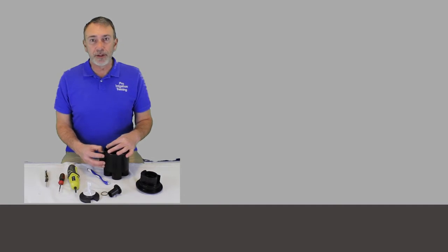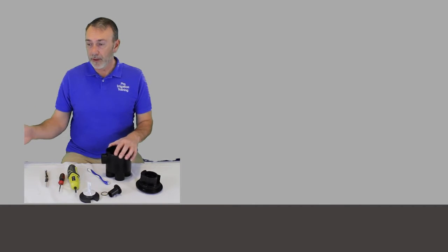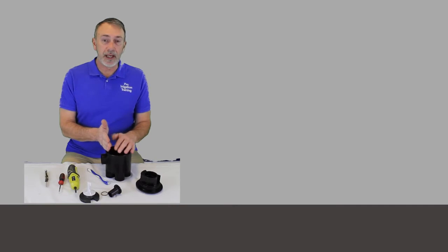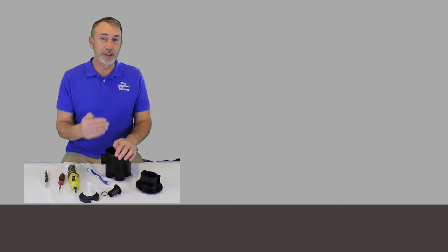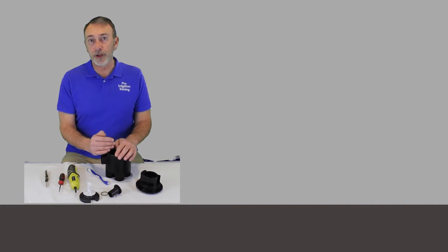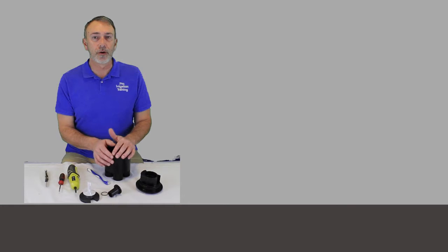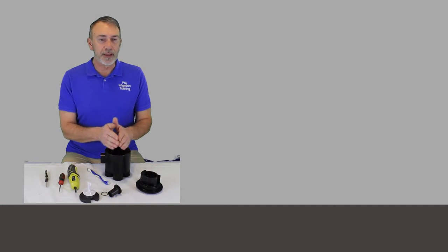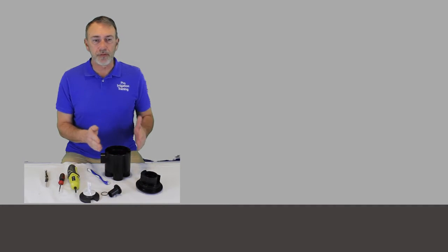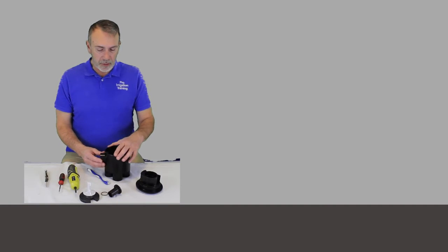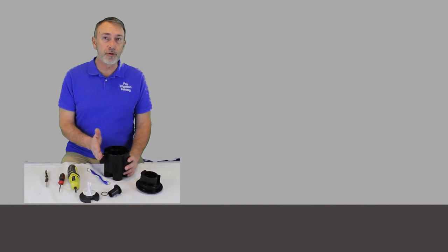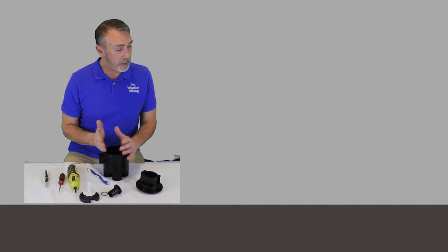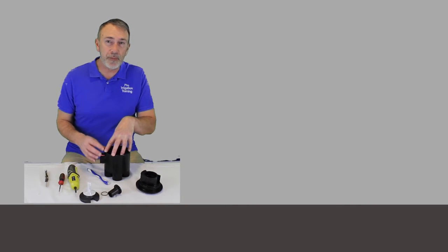On pumps, I like to mount a pressure gauge on the pressure side, between the pump itself and this. I like to put a pressure gauge on that side, but on the suction side, you should put a threaded fitting that you can put a vacuum gauge on. I generally don't leave a vacuum gauge on all the time, but I like to put a threaded fitting on there to put a vacuum gauge on it for troubleshooting purposes. Because if you don't have steady flow to them, it can cause some problems, especially with skipping zones. We have the problem of it skipping zones.